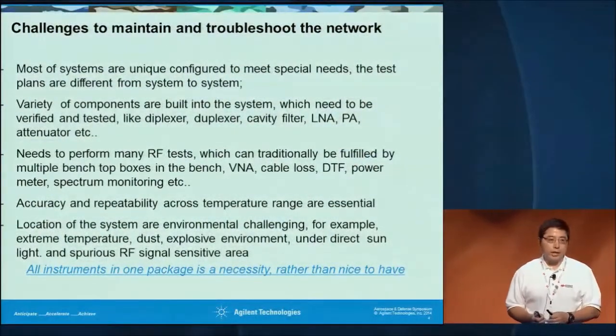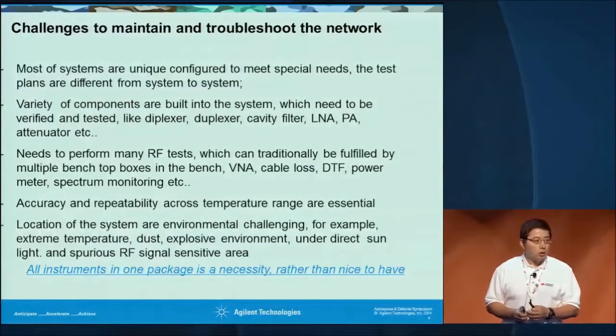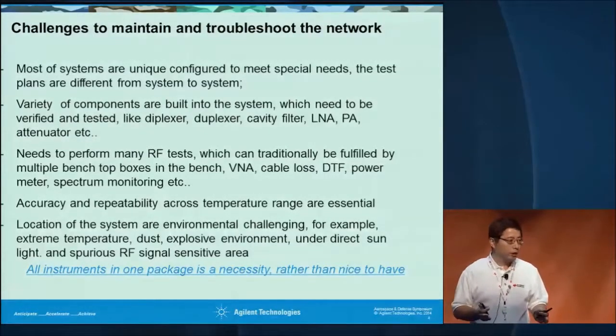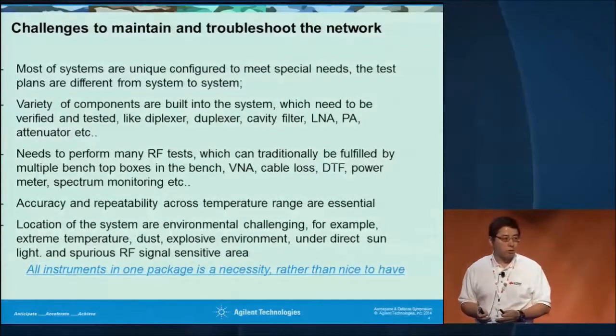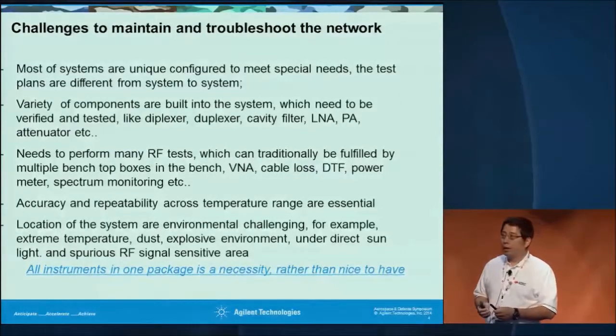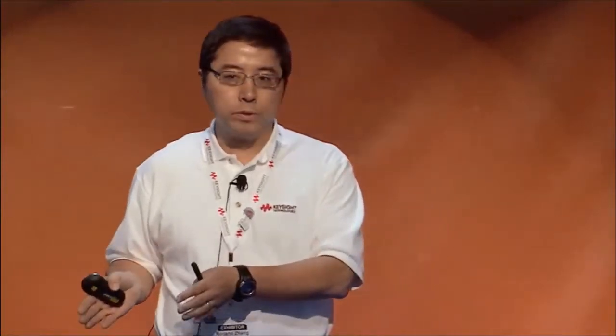One of the key challenges for a critical communication system is that most of these systems are unique — not mass production. So each system may need to be tuned separately. There are a lot of components built inside the system like filters, diplexers, duplexers, and amplifiers. One of the key aspects, technically speaking, is that people doing this type of system always want to make sure their filter or amplifier measurements in the field match what they're doing inside the lab. That's a particular challenge when you bring instruments to the field.